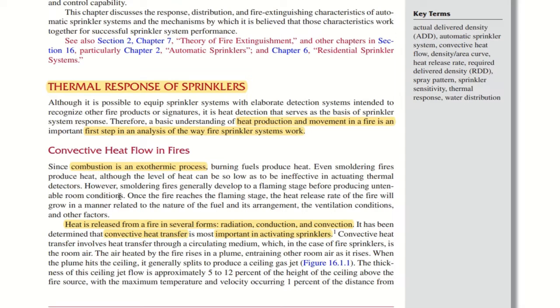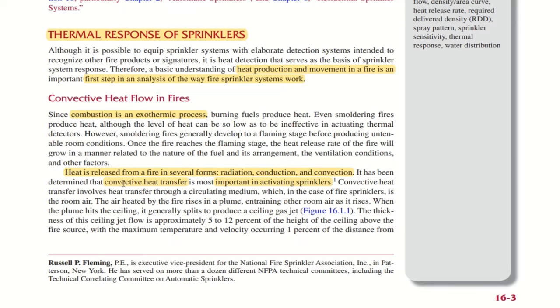However, smoldering fires generally develop to a flaming stage before producing untenable room conditions. Once the fire reaches the flaming stage, the heat release rate of the fire will grow in a manner related to the nature of the fuel and its arrangement, the ventilation conditions, and other factors. So heat is released in several forms from fire, such as radiation, conduction, and convection. So whenever you have a question in your exam related to the thermal response or the radiation, conduction, or convection, you need to check in section 16, chapter 1.